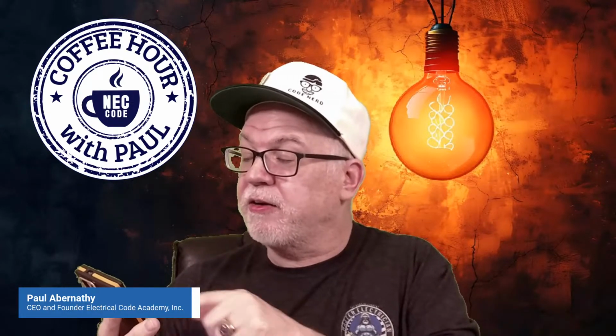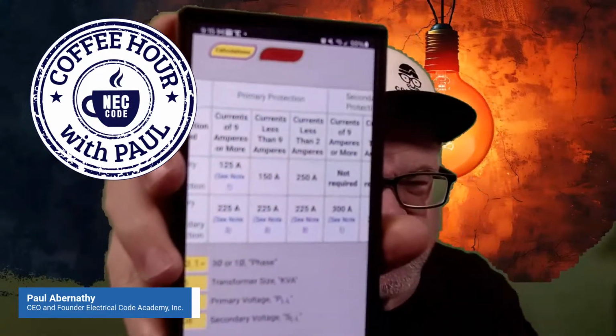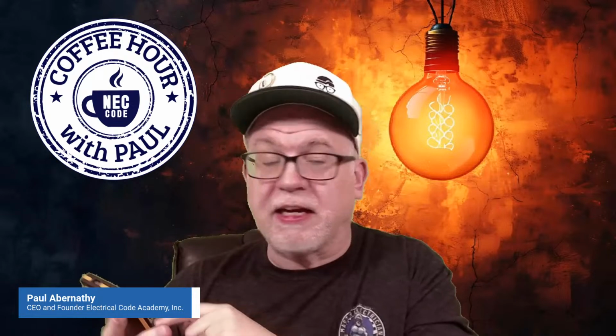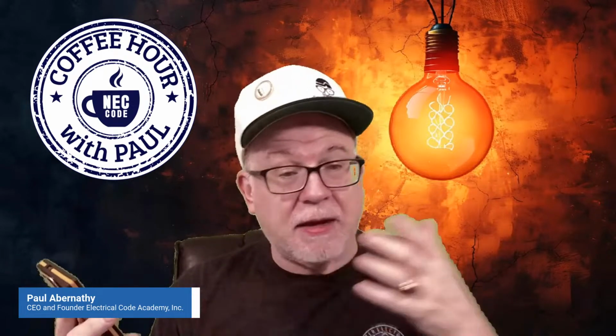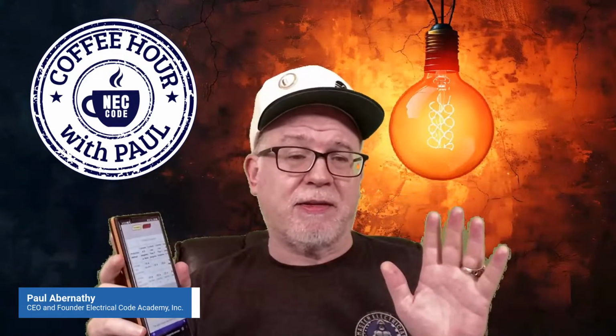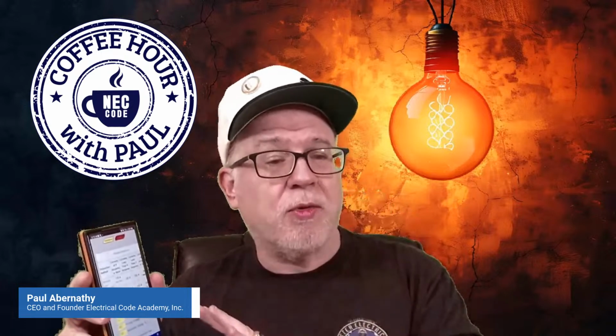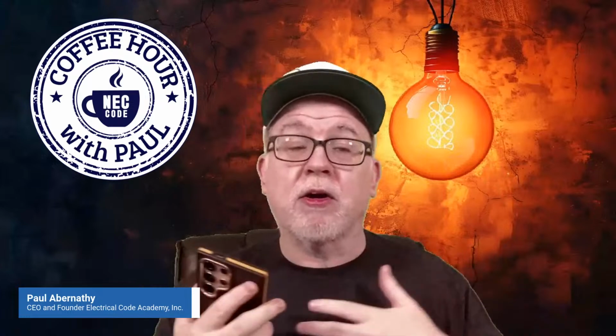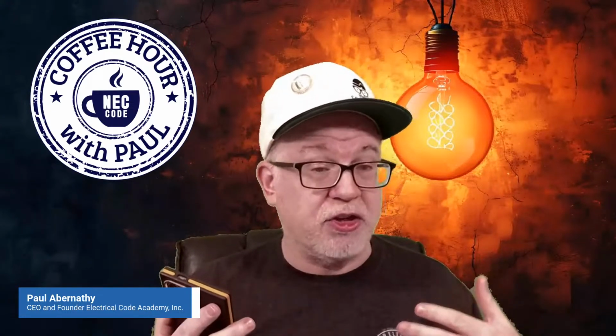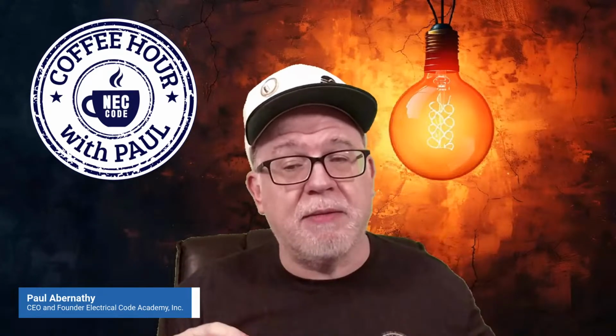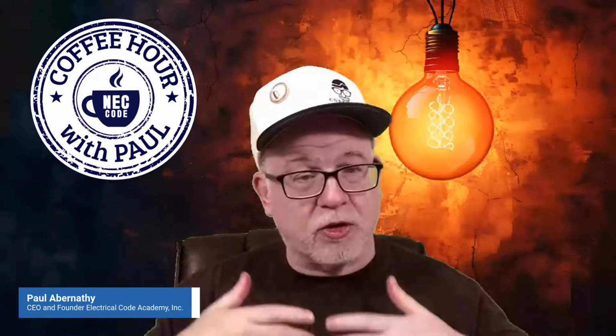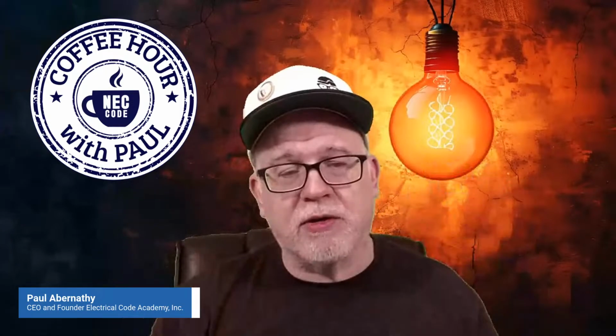And you remember what I said earlier, so I'm not full of crap. See where it says right here, 300 amps? That is the maximum that you could go on the secondary. Although that transformer can't put out that much, nothing prohibits you from going up to 300 amps. But in the real world, with a 75 kVA, you're probably going to supply a 200 amp. At the far worst scenario, you're going to be at 225. You're still only going to be able to get 208 amps out of that transformer. But you could load it, you have no headroom on it, and it could prematurely cause it to break down over time. So you want to size your transformers accordingly based on the loads that you're going to be putting into it. That's for a whole different story.